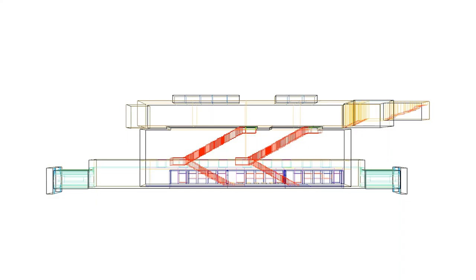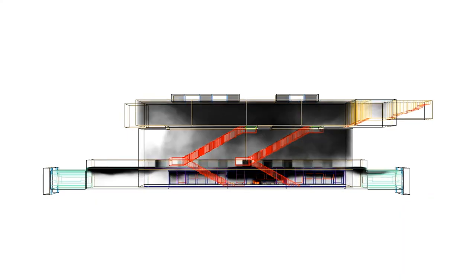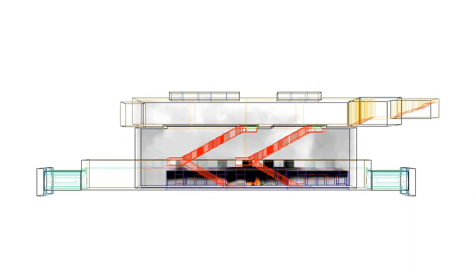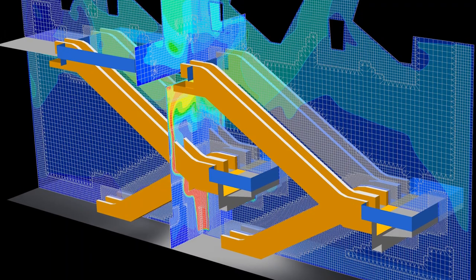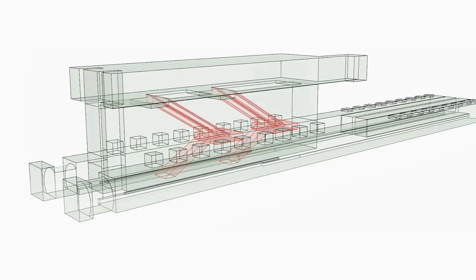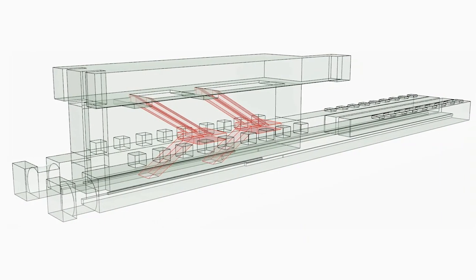We had platform screen doors, which helped a lot. So then we were able to extract from directly over the train and minimize how much smoke gets into the station as well at the same time. So you could have very direct extraction from right above a train fire, which really helped in reducing the fan sizes. The fans are only used during emergency or congested scenarios. So we're designing a metro system where we can ventilate through piston effect, which is the effect of a train passing through a tunnel and that self-ventilates.